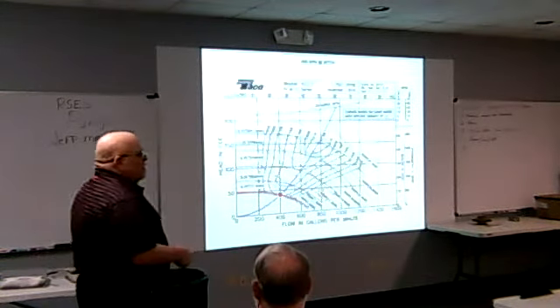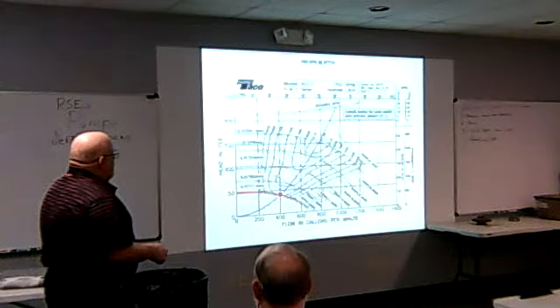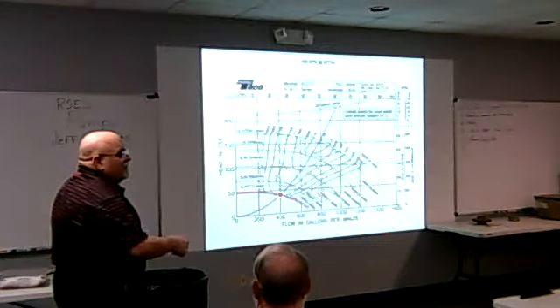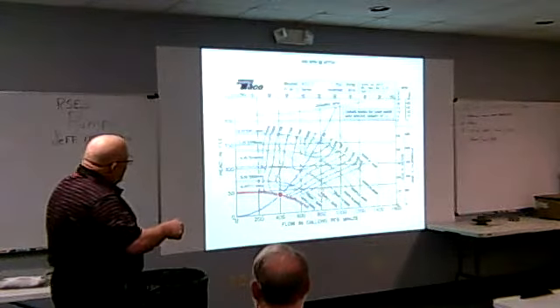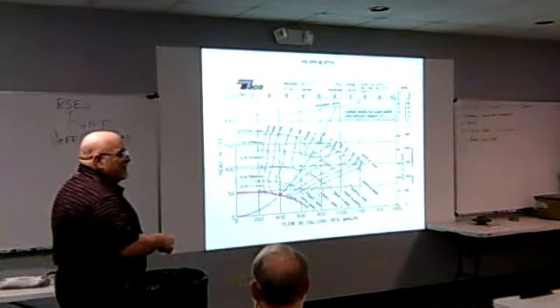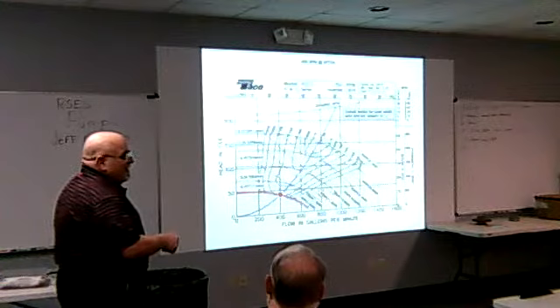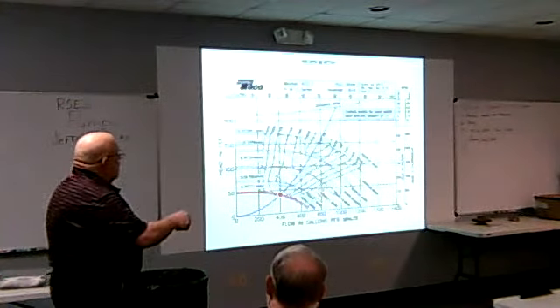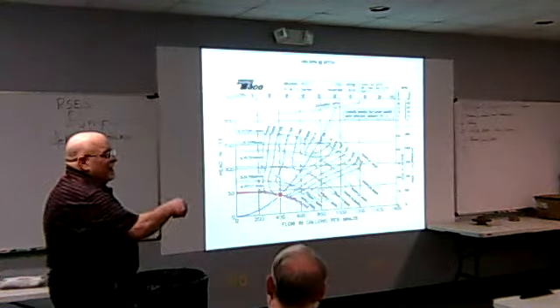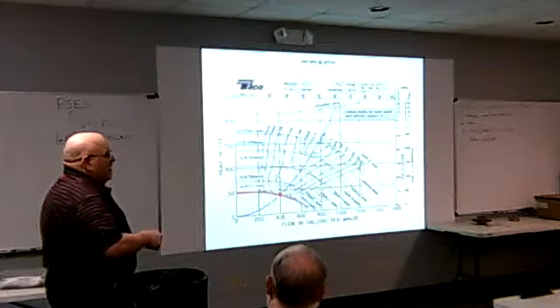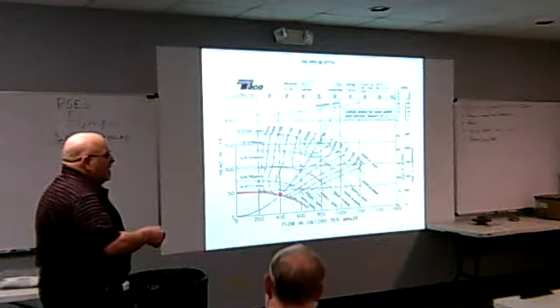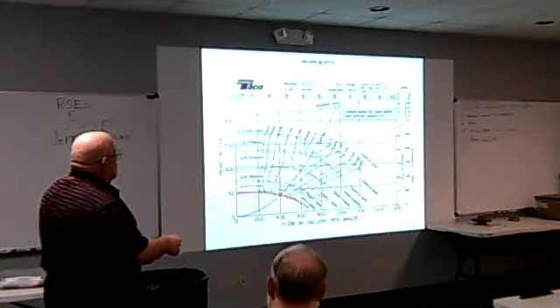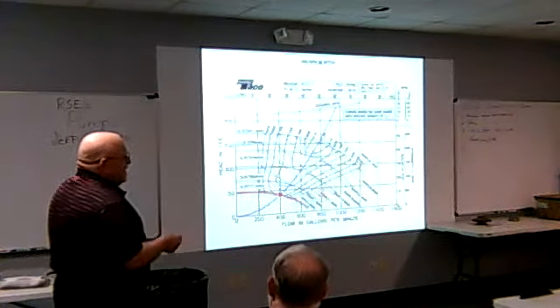A lot of people take a pump curve and they just go, oh, I'm at 40 feet of head. This is where I'm going to operate. I'm at 40 feet. No, you have to have the system curve. I'm operating on the system curve, not out here. I can't guess that way. I have to have an operating point to lay this curve to find out where I'm really in. I can't just arbitrarily pick and say, well, I have this impeller, what does it matter? The curve's back here. I can't get there from here again.